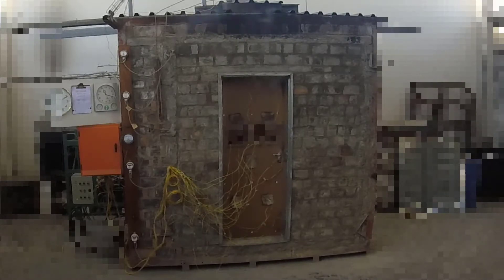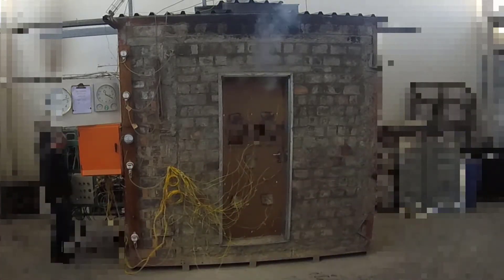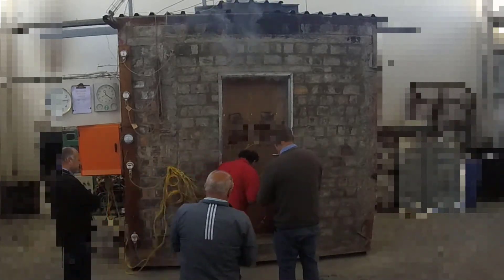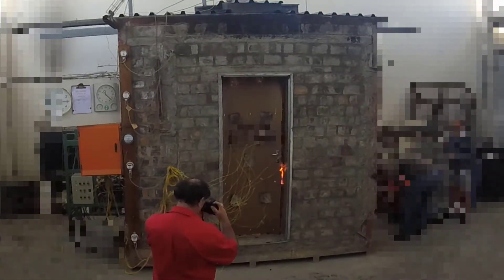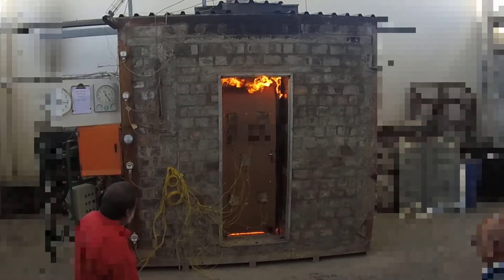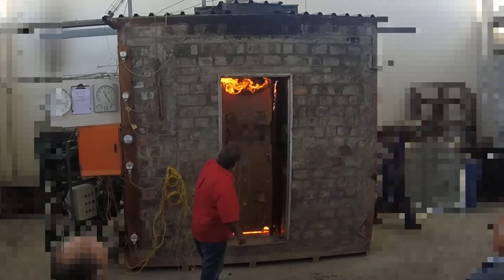To understand furnace testing, let's start with a real-life test. Here we have a door where the client was hoping for a one-hour fire rating, but the door failed in around 15 minutes. The video is sped up as the door is progressively exposed to hotter temperatures inside the furnace, following the standard fire curve. The door starts curling and peeling away, then you have flame-through and overall failure.